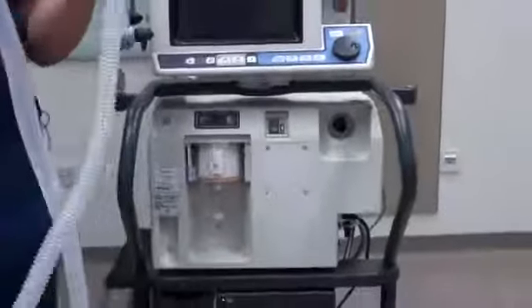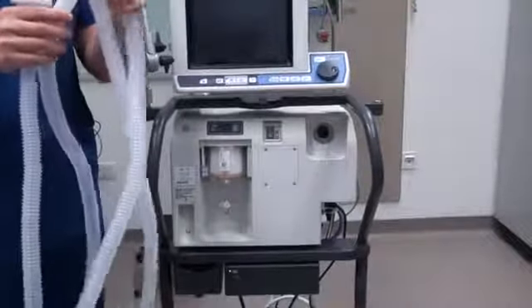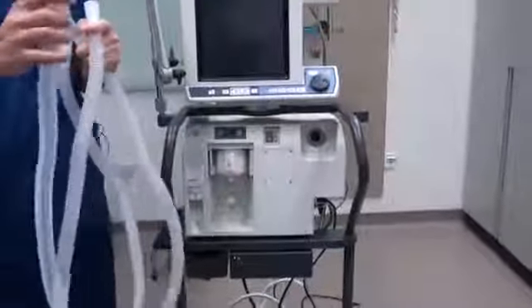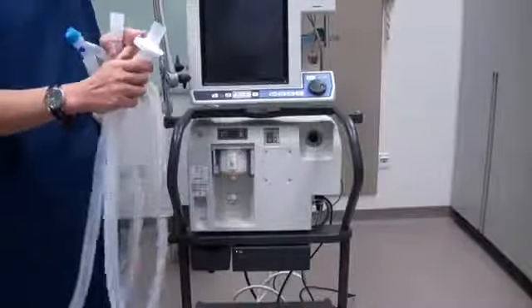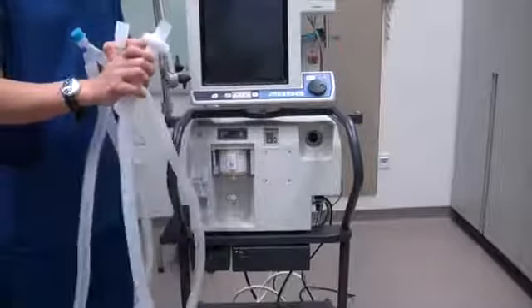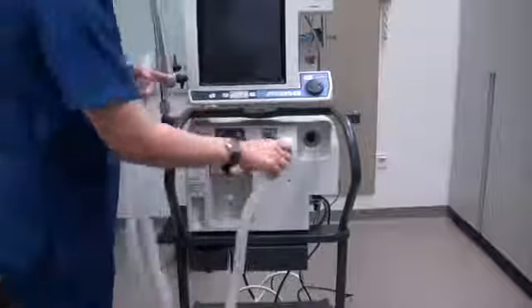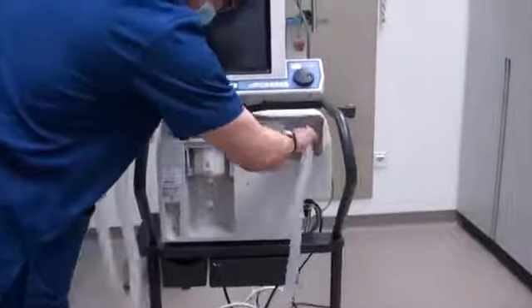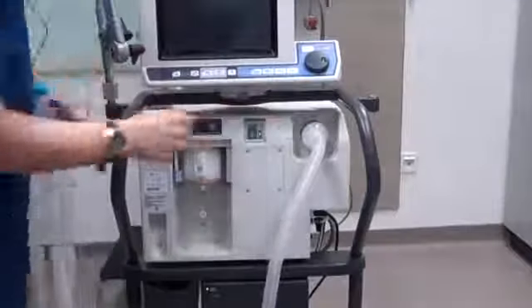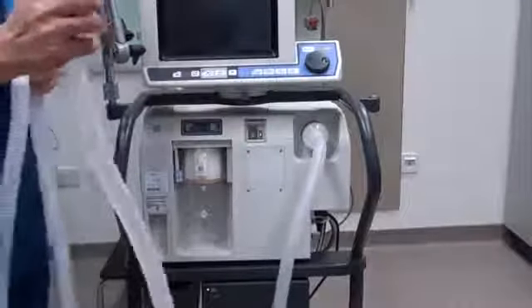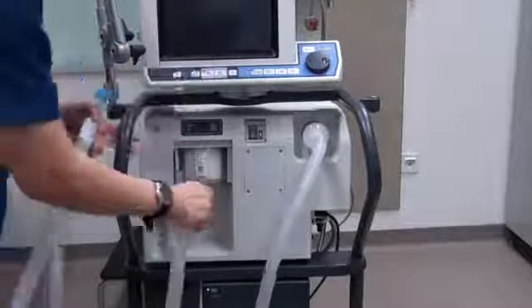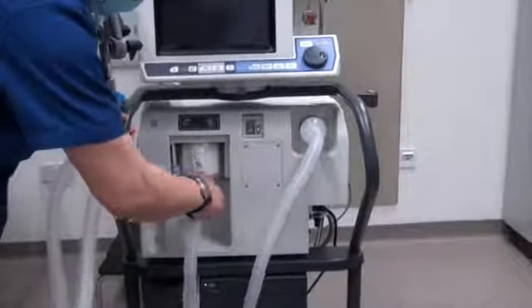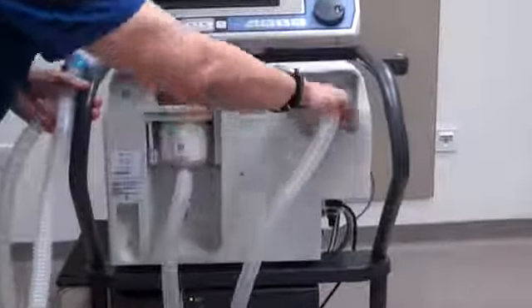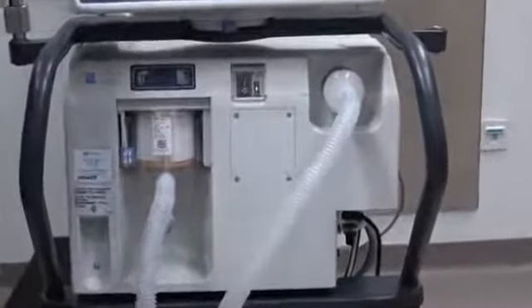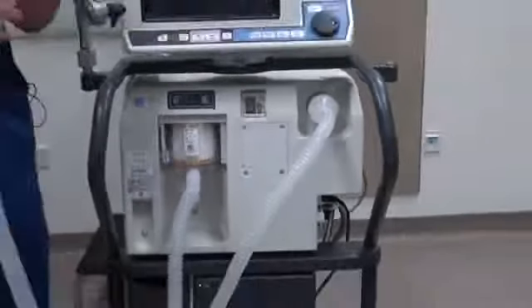The second component is putting in the inspiratory and expiratory limb, which is connected to a wye connector. One component will be the inspiratory limb. There will usually be a bacterial filter that comes together with the inspiratory limb. This will be applied to the inspiratory inlet. The second component will be the expiratory limb, which will be connected to the valve. Make sure that the connections are tightly screwed in. The circuit usually comes with a cap, which we'll leave on at this moment.